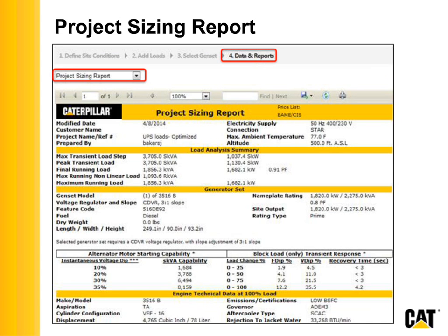Do you remember that I mentioned that SpecSizer is a full transient response tool? These are not fudge factors that we use for transient response. We actually factory test our gensets. Actual iron, I get that transient response. Remember I mentioned that we get it at not only a standard slope, but an optional slope. Well, that is loaded into the tool. So here you see the transient response of your selected genset at 25% load change increments.